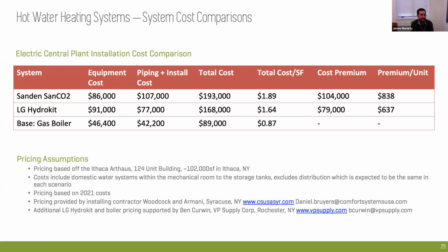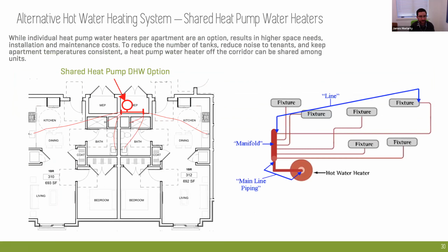The flip side is that operating cost wise it might be about neutral to operate these systems, because gas is still fairly inexpensive, and the electric systems, while efficient, might be about cost neutral to operate. So if you do have a gas system, one key would be to make sure you're designing it to be swappable in the future, so that 10 years from now, when maybe there are better technologies or systems that are more swappable, that would be something else to make sure to design in.